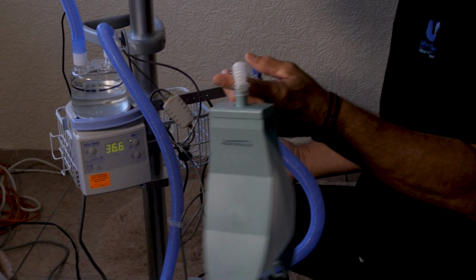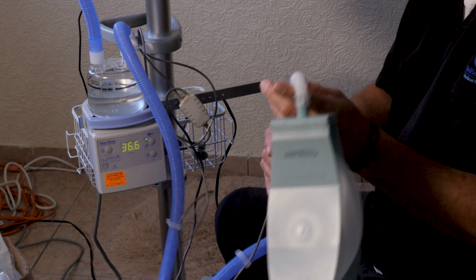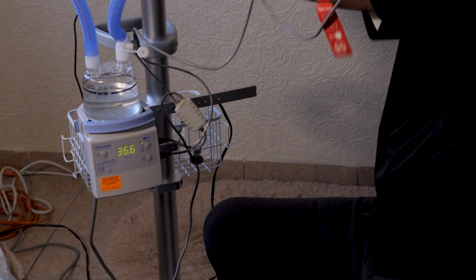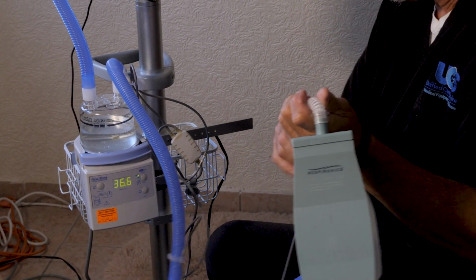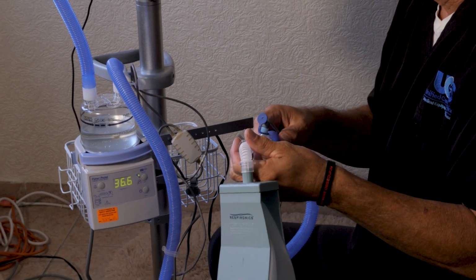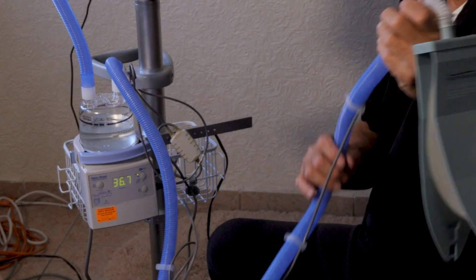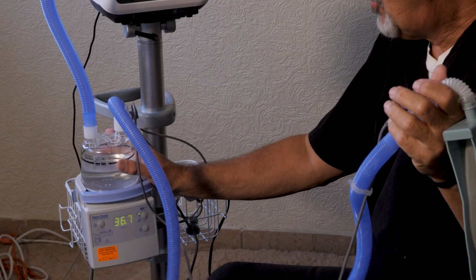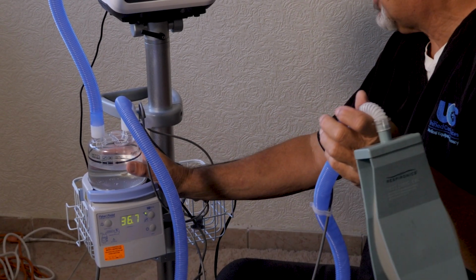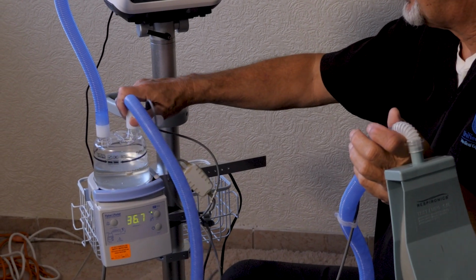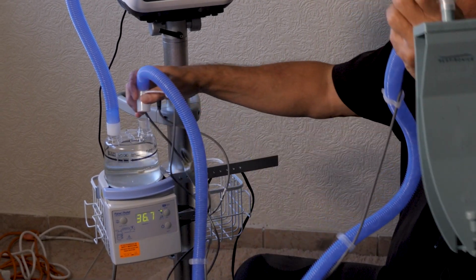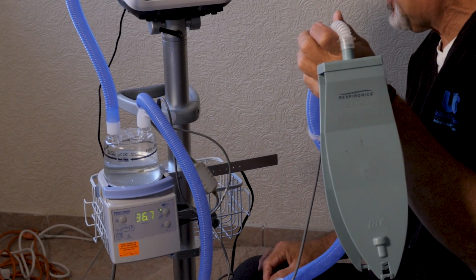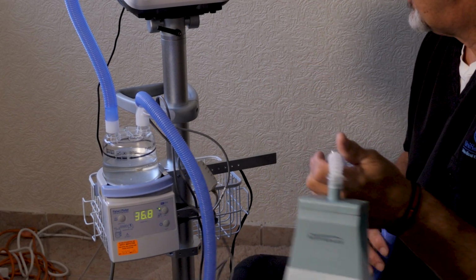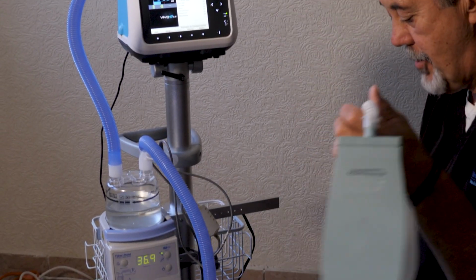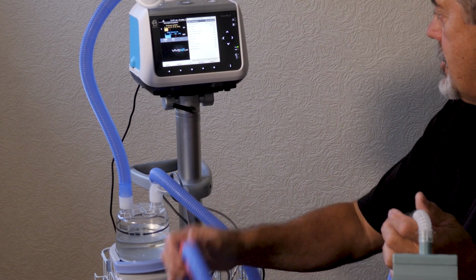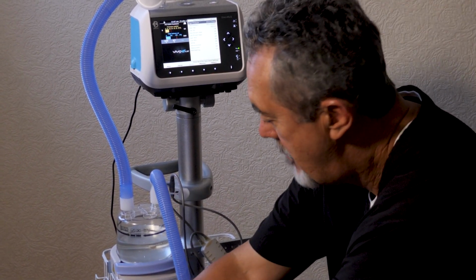There's two ways you could do this. I don't recommend that you actually drain the water back into the water chamber, because if there are secretions that have moved into the circuit, then what's going to happen is you're going to contaminate that water that's in the water chamber, because you're going to move the secretions back down into the water chamber. So what you could do is you can actually detach this here, empty the water into a bucket, okay, and that's probably the best way to get rid of the water that's in the circuit. So that's your high pressure alarm. Also make sure that there's no kink in the tubing. That could also cause a high pressure alarm.